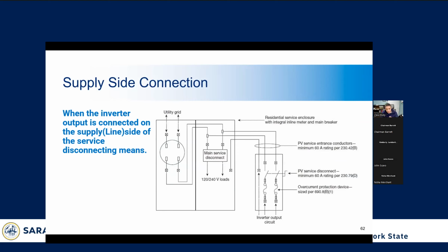Now we'll talk about the supply side connection. This is when the inverter output is connected on the utility side of the main service disconnect. This is sometimes referred to as a line side connection or a line side tap. And since the supply side connection is very similar to a new service entrance, the NEC requires that the disconnect be rated for such. And you need to have conductors rated for 60 amps going from your inverter output to where they connect into the supply side connection. And I believe the main service disconnect also has to be rated for 60 amps. Yep, so I think that's everything for this slide.